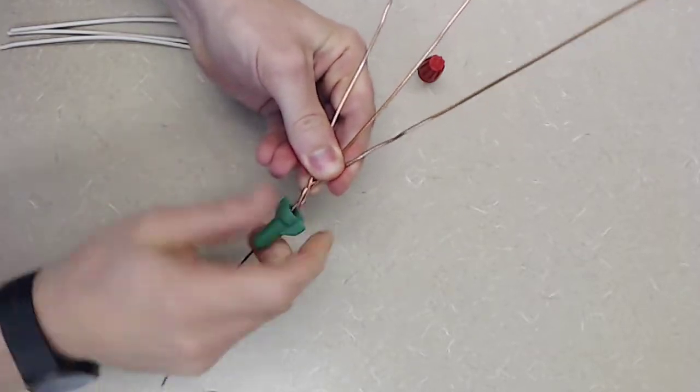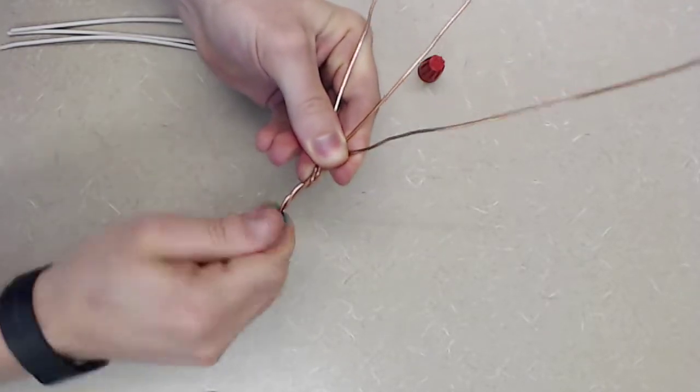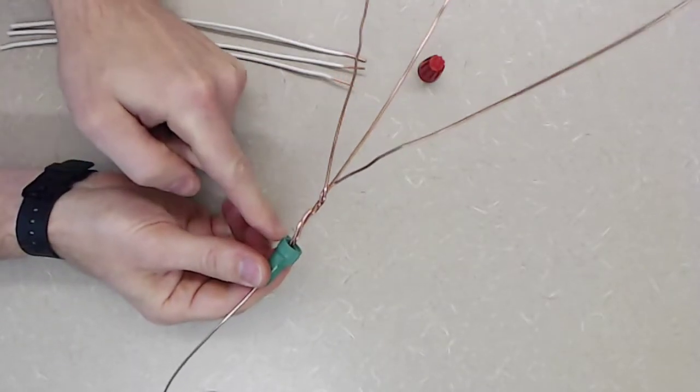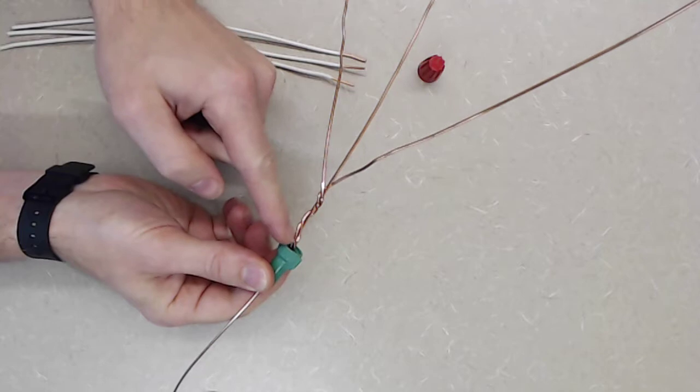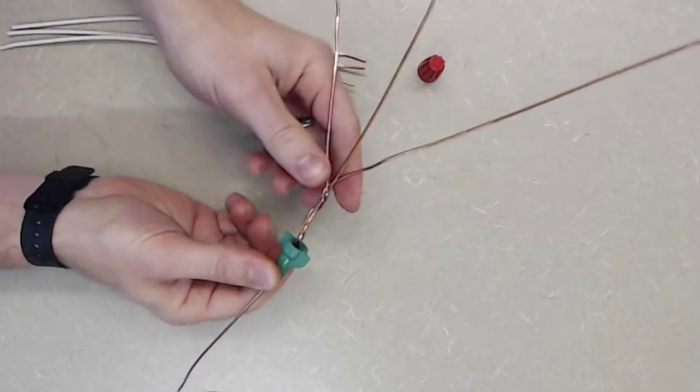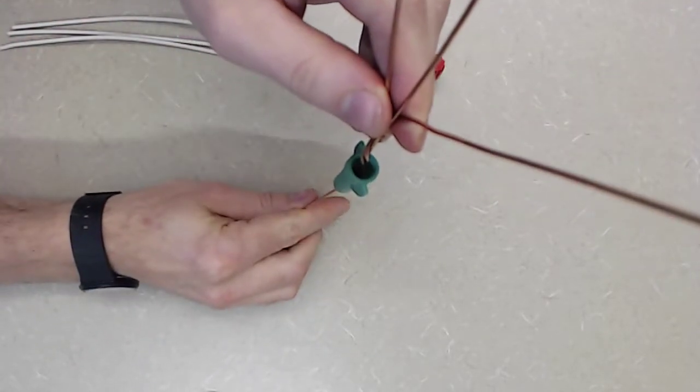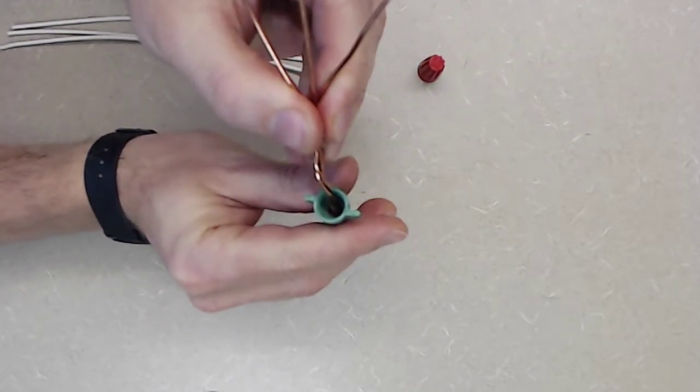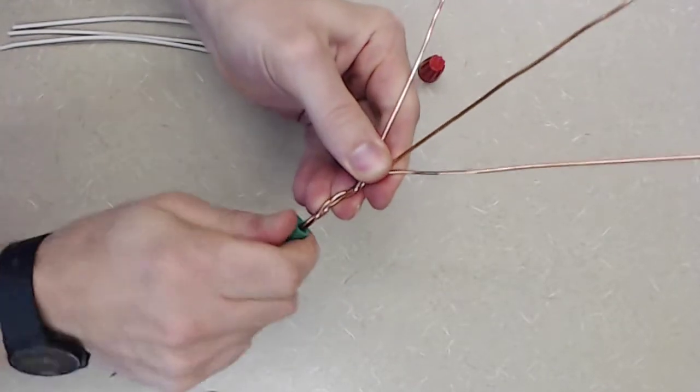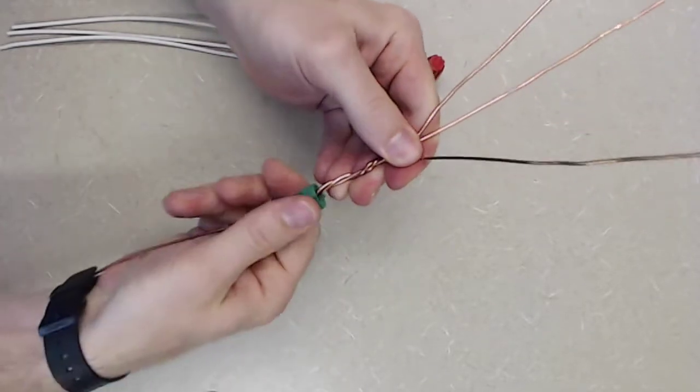Now what I want to see in the lab is really twisted wires outside of that wire nut to ensure that you have them mechanically twisted together. Inside there, of course, tough to see because of the light, but you'll have the wires twisted together fairly tightly.